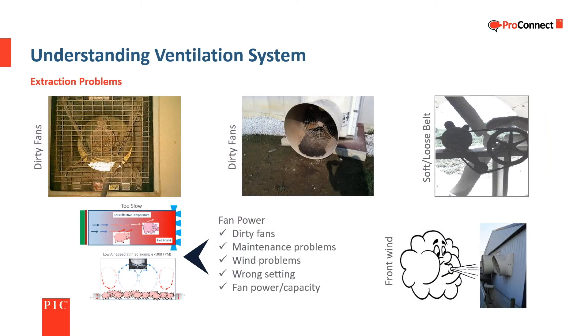The ventilation system depends on fans to move air out so fresh air can enter. Extraction problems can be caused by a variety of things such as wrong controller settings, dirty fans and louvers, wind interference, maintenance problems, as well as fan power or capacity. Air speed that is too low results in incorrect air mixing and poor ventilation, both with ceiling inlets and in tunnel ventilation.